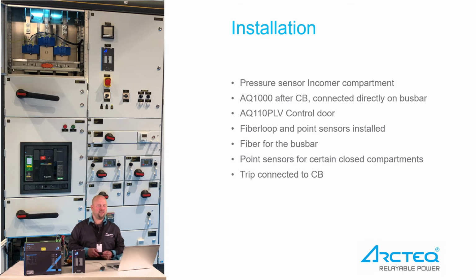Here is one example from the low voltage board. AQ1000 is installed here in the bottom left under the circuit breaker. On top left there are busbars, which come from the transformer. It goes to the circuit breaker, and under the circuit breaker the busbars go to the horizontal and vertical busbars inside the panel.